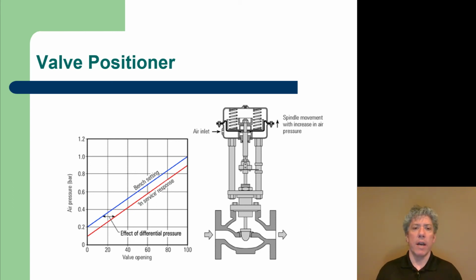So one more thing about valves before we move on. There's a couple of different considerations. You've seen only a small fraction of the different types of valves that are available. One thing to note about valves is that it's really important to choose the right valve for the right application. There's a bunch of considerations. Cost is always number one. If you can't afford it, you can't buy it, right? So cost is certainly a consideration, but the temperature range that the valve has to operate in is very, very important. The chemical compatibility between the fluid flowing through the valve and the valve body, what it's made out of, is another huge consideration. Obviously, what's called the flow coefficient, or how much flow you expect through it. I mean, the valve for a 1 gallon per minute flow is going to be vastly different than a valve for 1,000 gallons per minute flow, right?